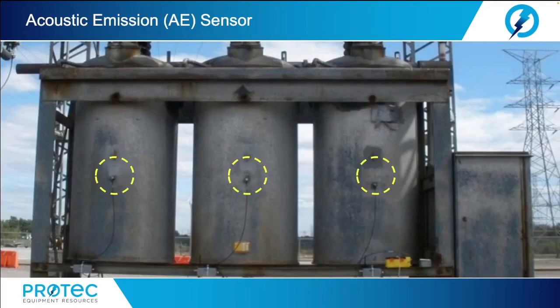All right, let's talk about an acoustic emission or AE contact sensor. The AE contact probe is ideal for detecting and localizing partial discharges in fluid dielectrics such as oil and SF6 gas compartments. This is sometimes called in-tank testing. Each time a partial discharge event occurs, an ultrasonic emission is produced at the site of the defect. If the defect is inside a sealed equipment, such as a transformer or SF6 compartment, the signal will usually not become airborne.